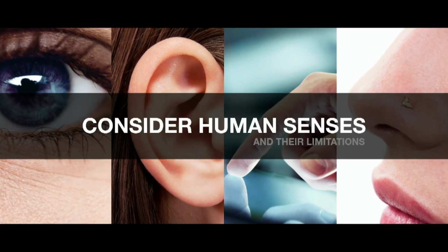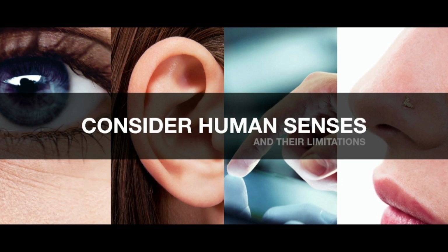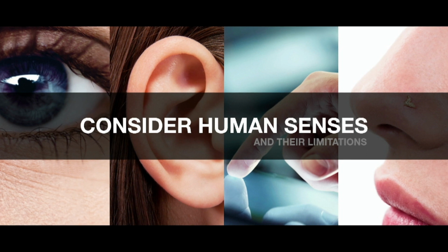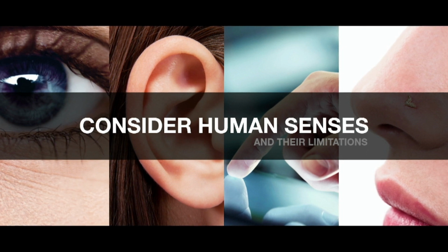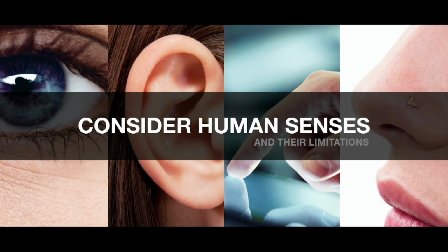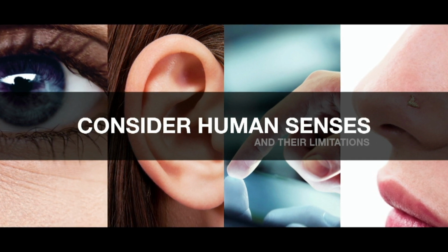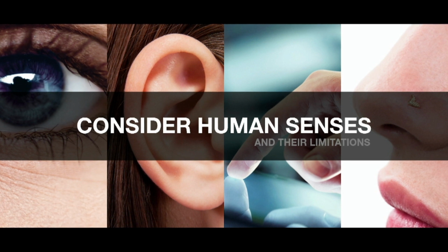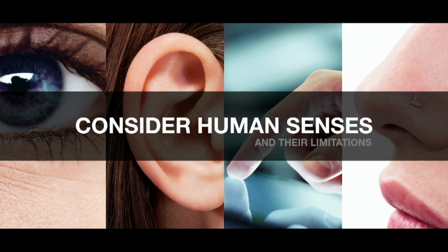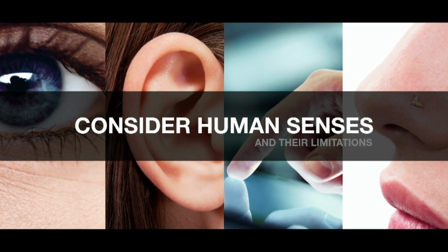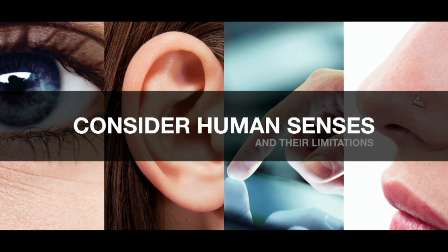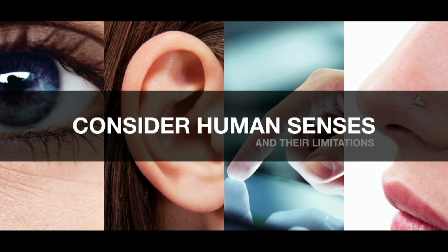So another thing to do is to consider all human senses and their limitations as well. As part of, let's say, a medical device used in surgery, for instance, or even any product really, we need to think about visibility. If there is a feedback loop based on one action within a product, is the indication or the feedback back to the user visible enough? Whether that's an LED or something on a touch display, is that being presented appropriately enough to know?